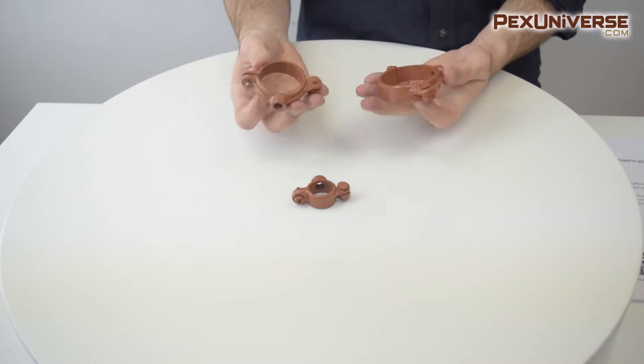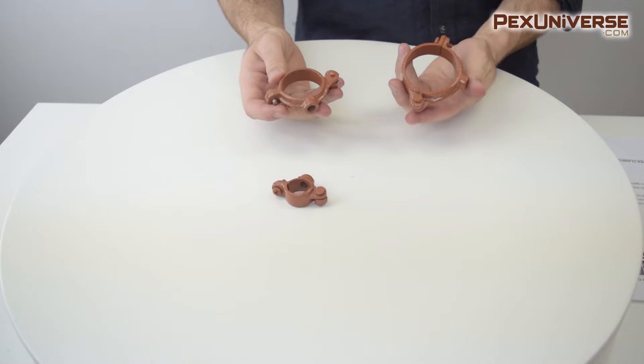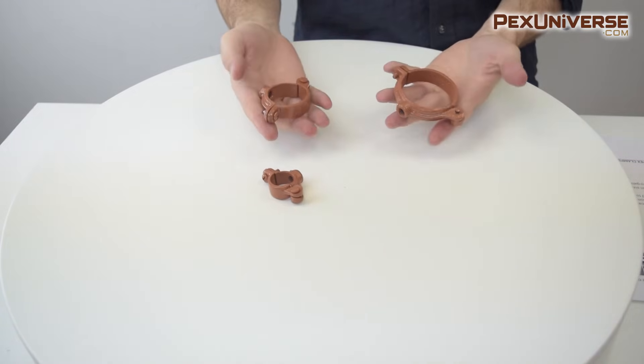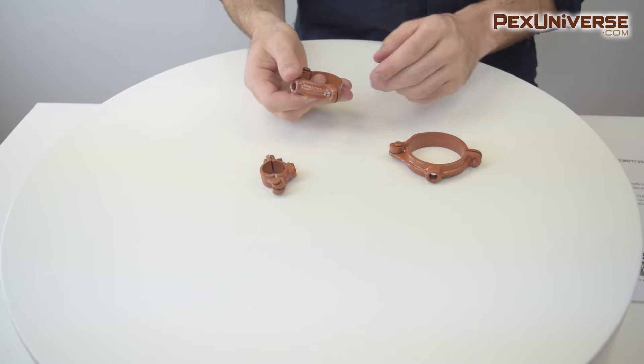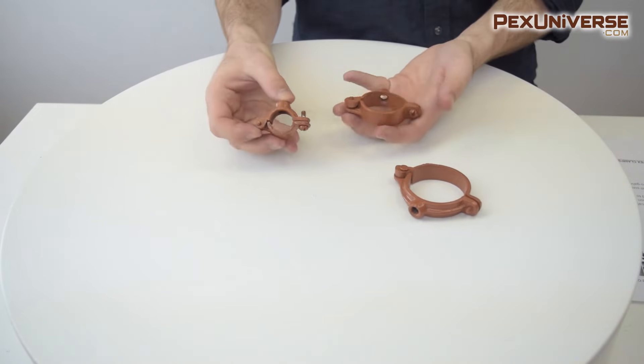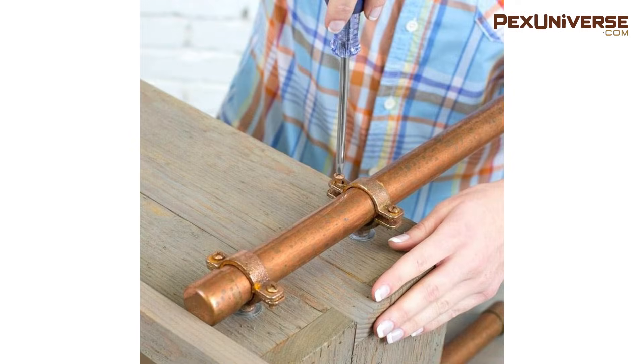Split ring hangers support vertical or horizontal pipe runs. They're used in combination with threaded rod and accessories to be attached to the wall, ceiling or beam. These come in sizes from 3/8 of an inch to 4 inches and in copper, plain or electro galvanized.